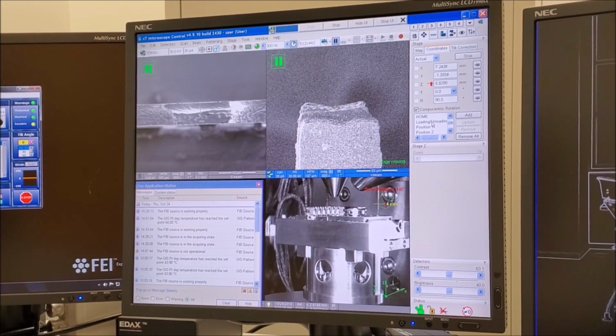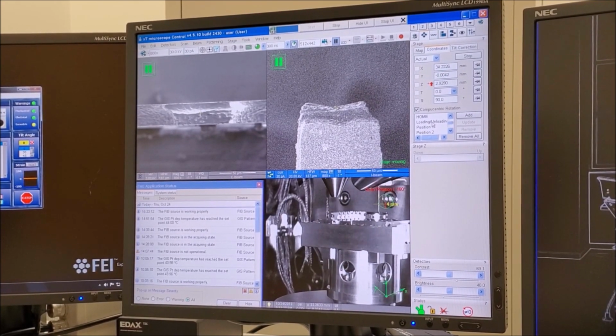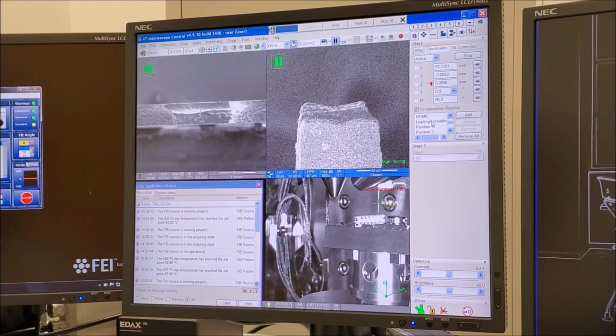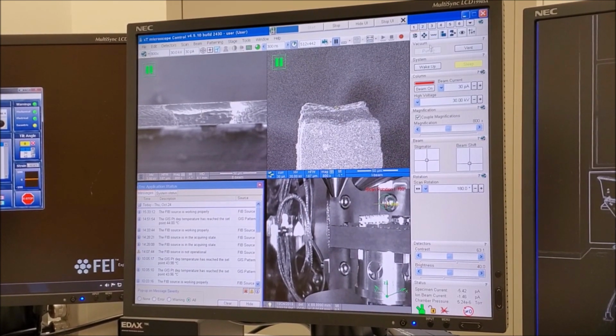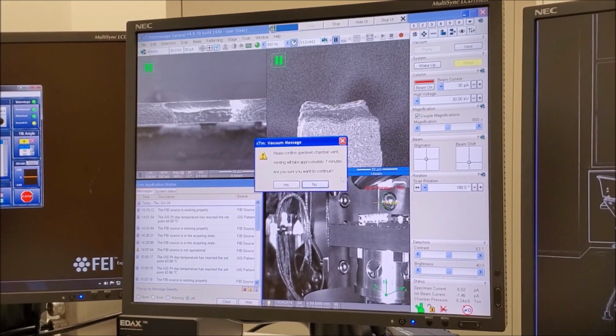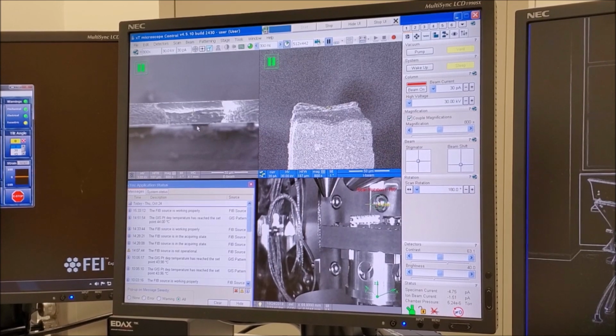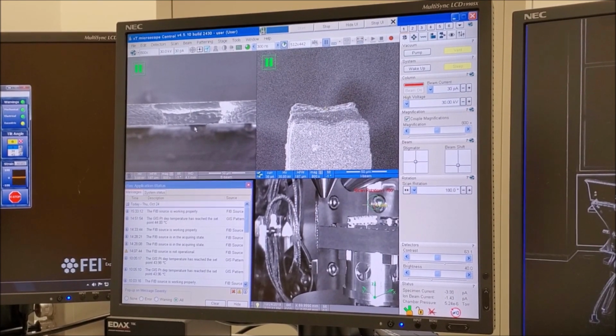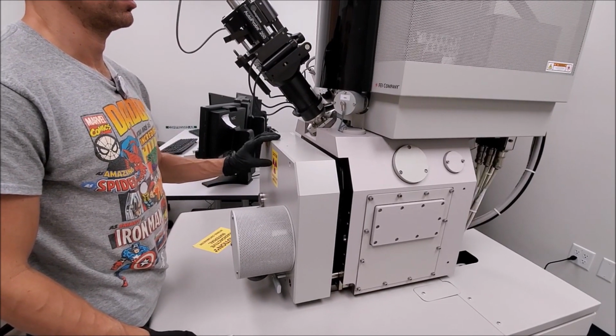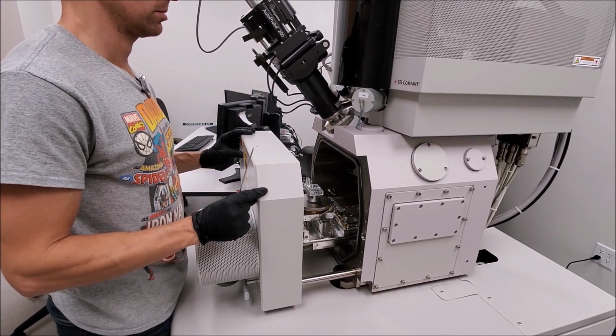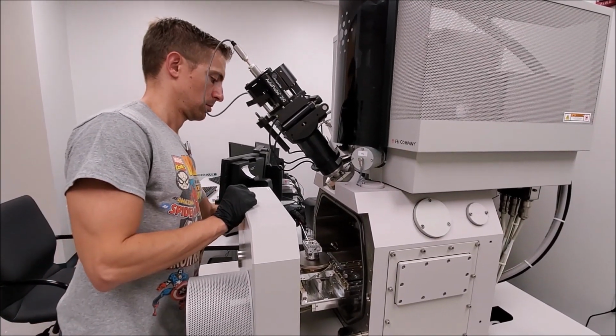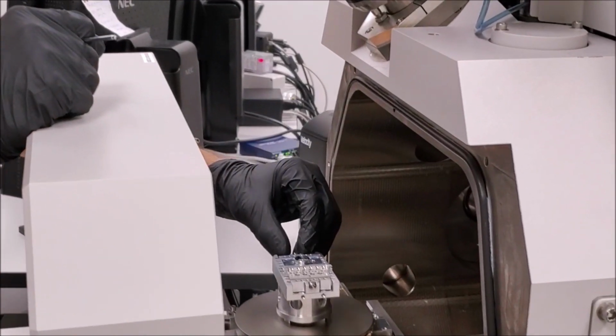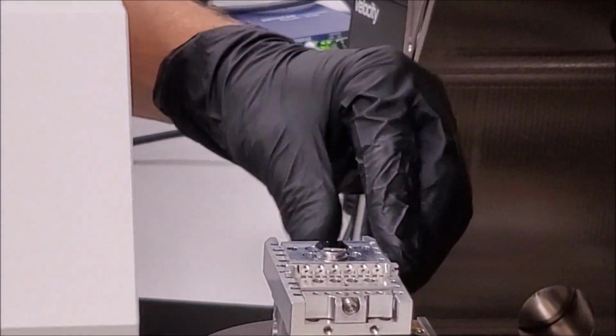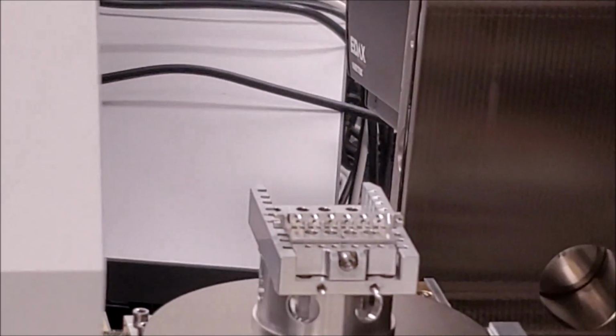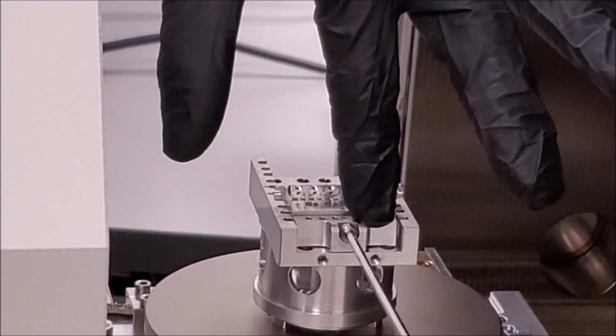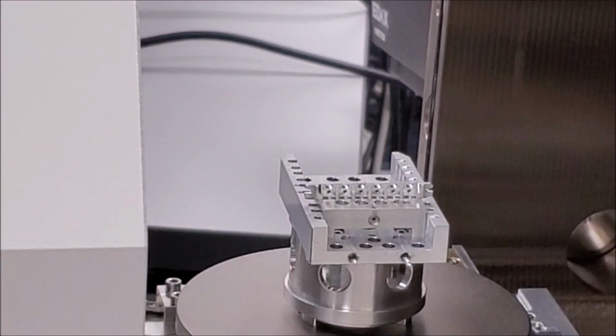Enter the navigation module and select loading unloading from the list of stored stage positions. When stage movement is finished, enter the beam control module and select vent to start venting the chamber. When the chamber is vented, gently open the chamber door, loosen the clamping bars holding each module in place on the universal mounting base, and then extract the modules. Then close the chamber door and pump back down under vacuum as described previously.